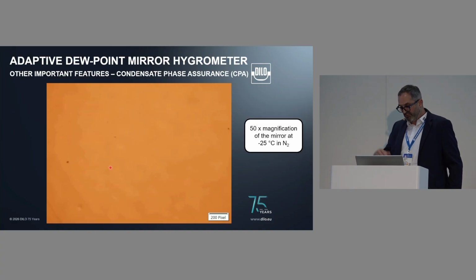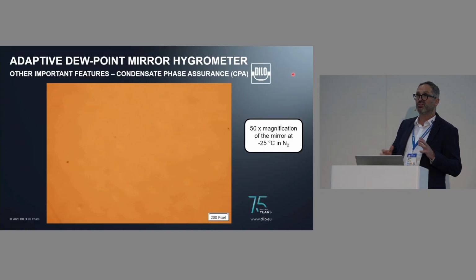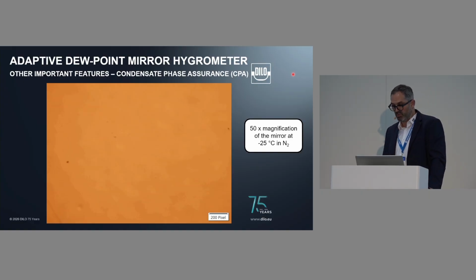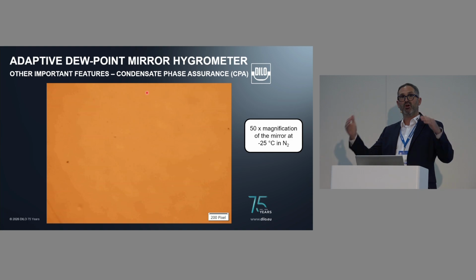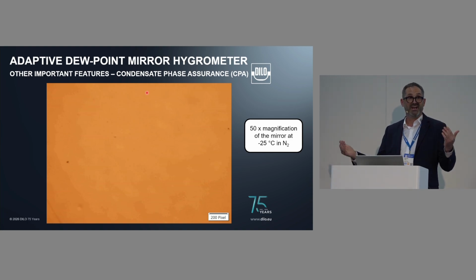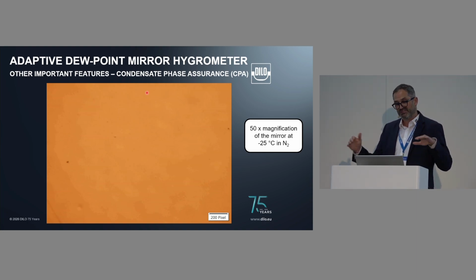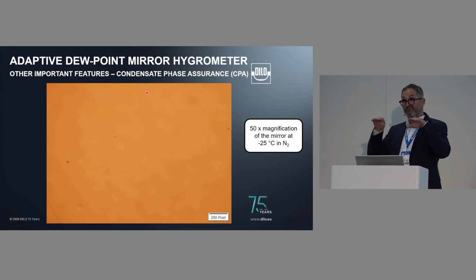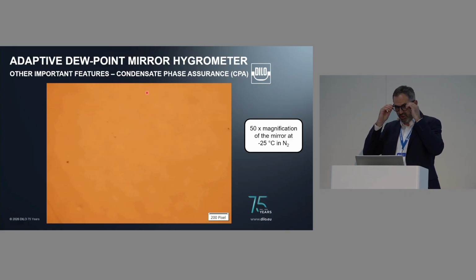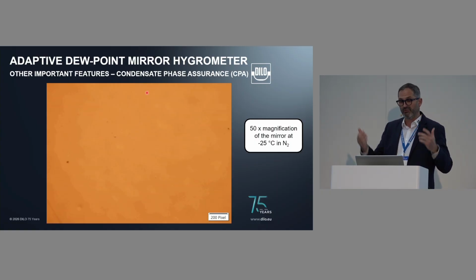And apart from the automatic gas detection, there are also some other important things to consider when you want to do a measurement with a chilled mirror hygrometer. For example, it is important to know whether the mirror has liquid or ice on it. Because if you know the phase on your mirror, you know if you should use frost point or dew point.